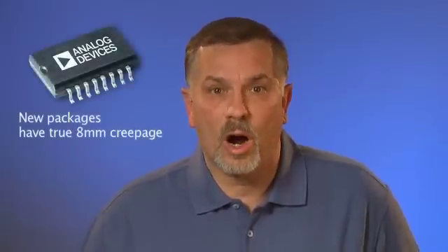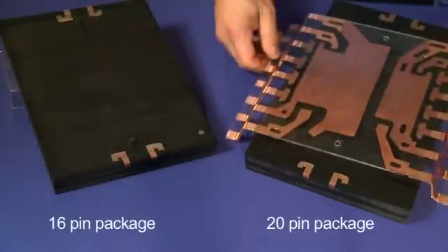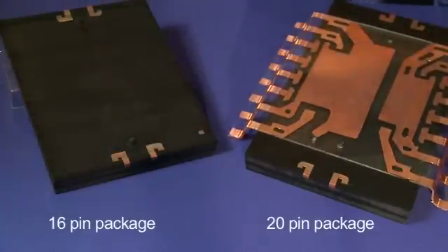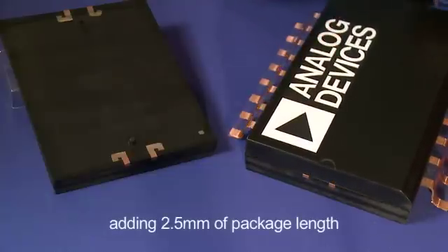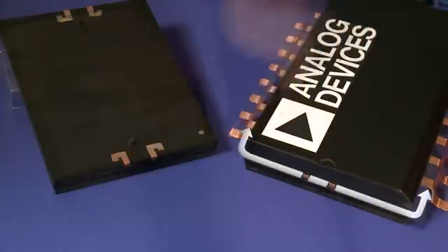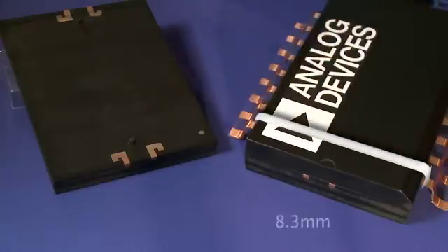ADI's new RI packages with reinforced insulation have true 8mm creepage according to IEC standards, and are within the JEDEC standard for manufacturability. To achieve 8mm creepage, we put our 16-pin lead frame inside the body of a 20-pin package, adding 2.5mm of package length. This increases the distance around the end to almost 10mm, and moves the creepage path from around the end of the package to over the top, where the creepage is 8.3mm.